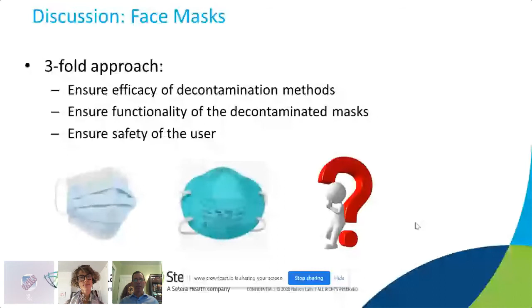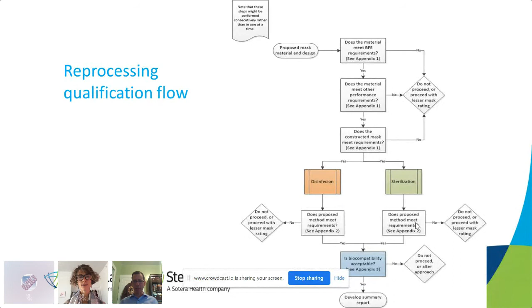First, how does the material function? Does the material function correctly after the decontamination processes? We test before, of course, so we have something to refer to. Then we have a disinfection and sterilization component down at the bottom there. And then after multiple disinfection and sterilization uses, or implementations, does it still meet the requirements? And lastly, is it biocompatible after either this disinfection or this sterilization process?